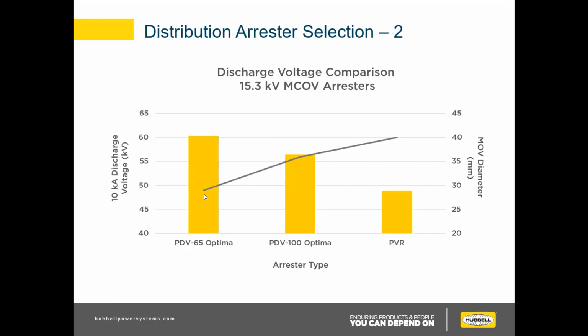So this is a discharge voltage comparison for our different distribution product lines. On this axis here, we have our discharge voltage for the same voltage system, 15.3 kV MCOV. This is our normal duty, heavy duty, and riser pole. You can see that the larger the diameter of the block, the lower the discharge voltage. So if you have some sort of specialty equipment that has a lower BIL than normal, it would be recommended to upsize from a PDV 65 to a PDV 100, or even from a PDV 100 to a PVR.